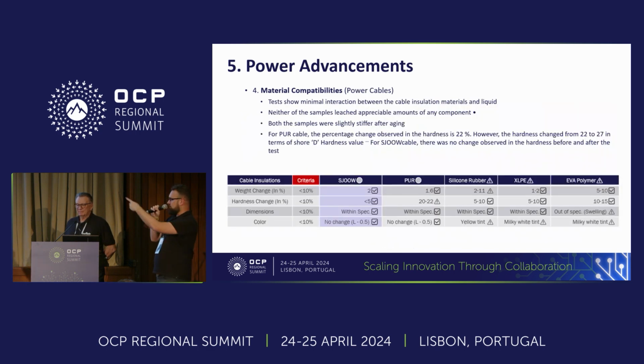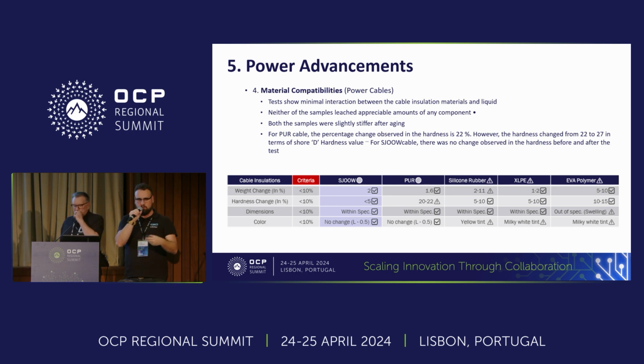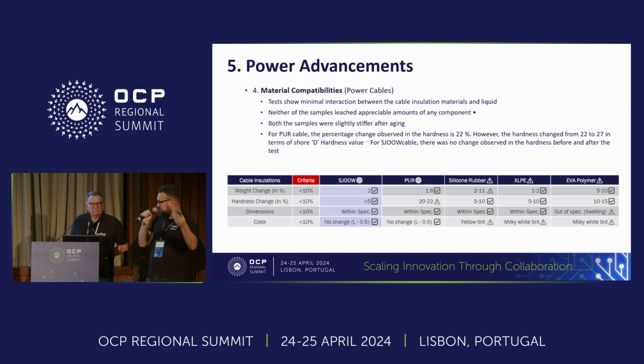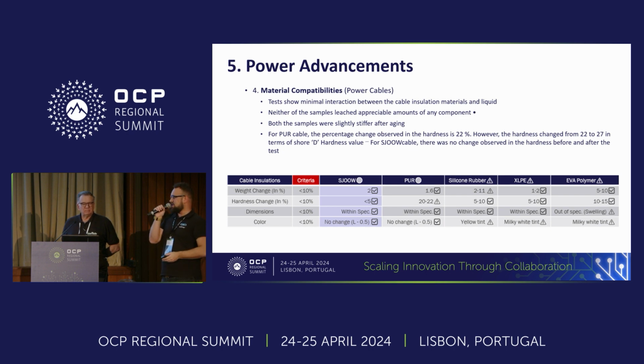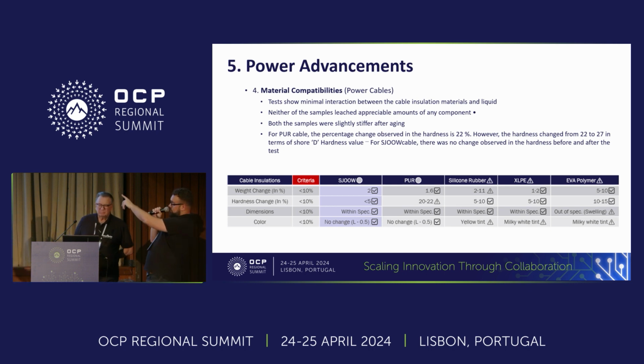So this is a bit more of that information. For example, the weight change—are the cables absorbing fluid? Are they increasing, stiffening, changing dimension or color? All of that we've been testing with really good results. PUR is probably one of the best elements we recommend typically for immersion, and SOOW—it's still a specification, but also a very good option for power and cable jacketing in immersion.